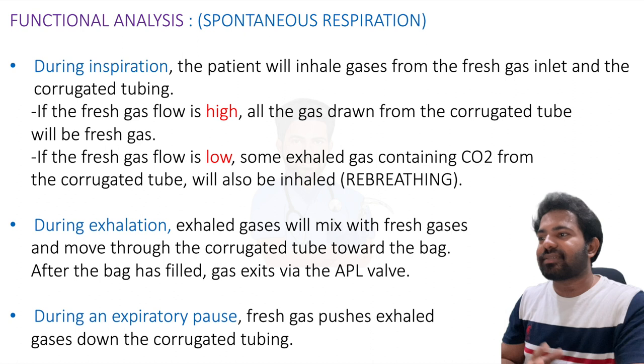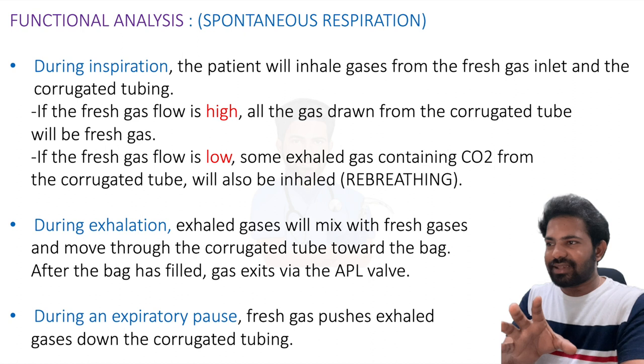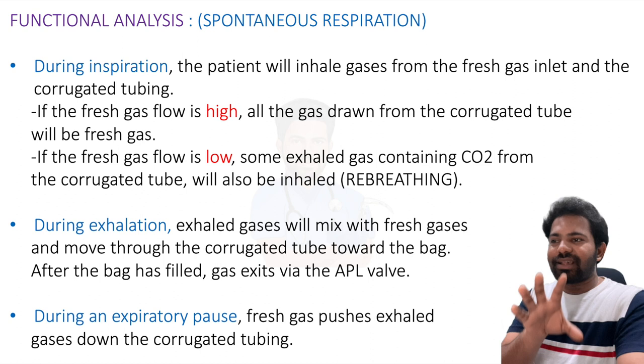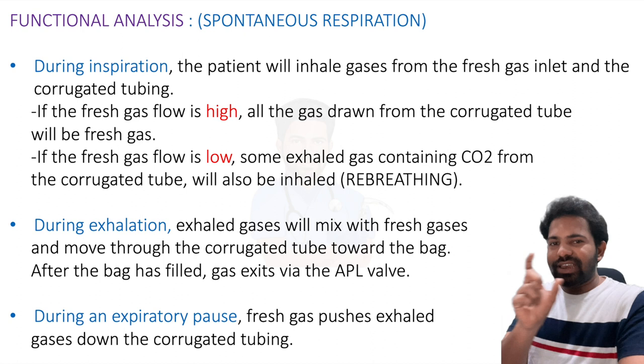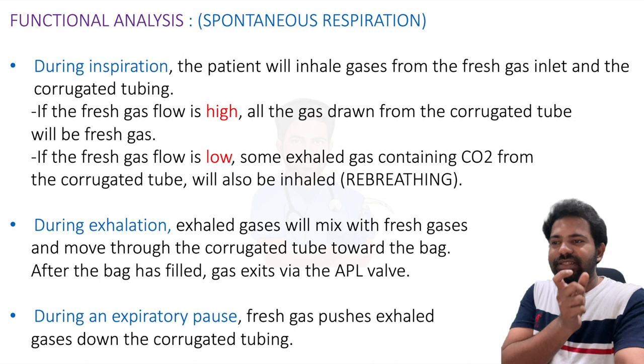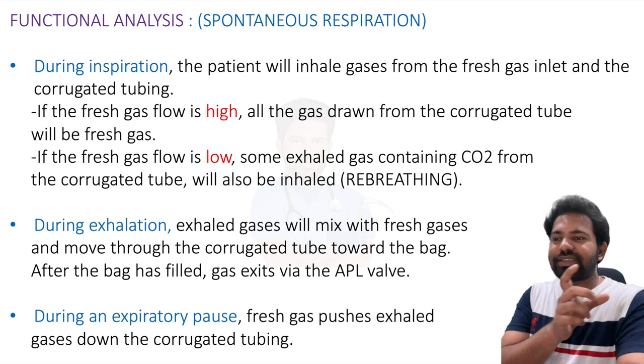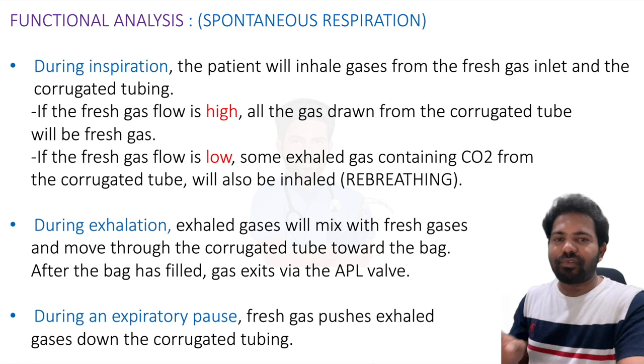During exhalation, the exhaled gases mix with fresh gases and move through the corrugated tubes toward the reservoir bag. After the bag has filled, gas exits via the APL valve. During the expiratory pause — since each expiration is not immediately followed by an inspiration — the fresh gas pushes the exhaled gases down the corrugated tubing and through the APL valve to the outside.